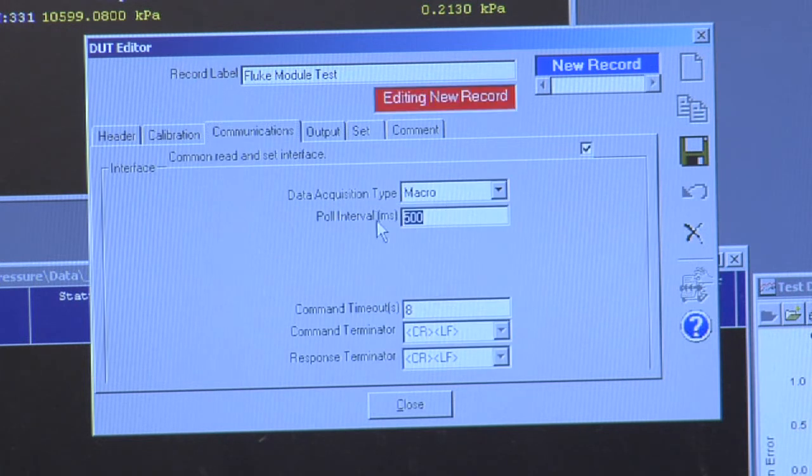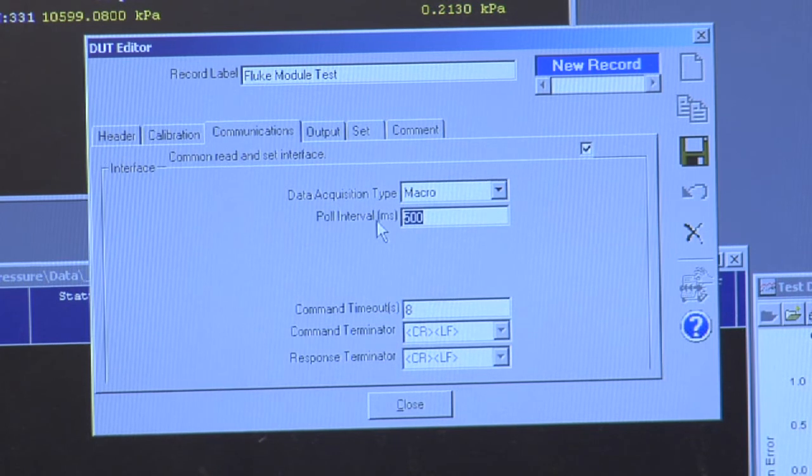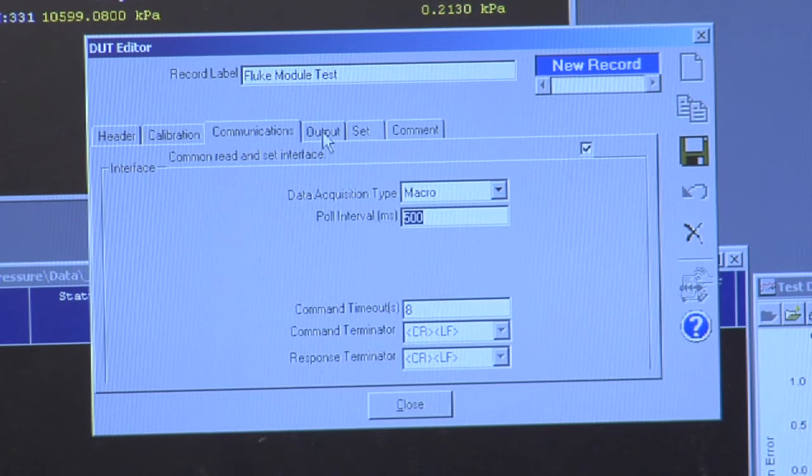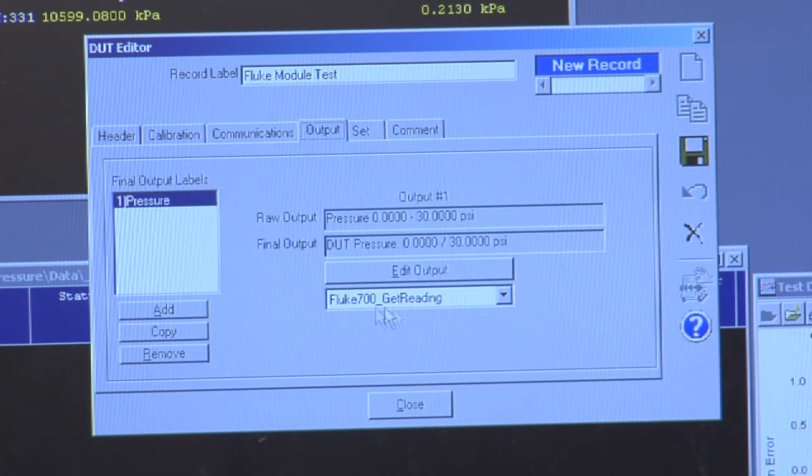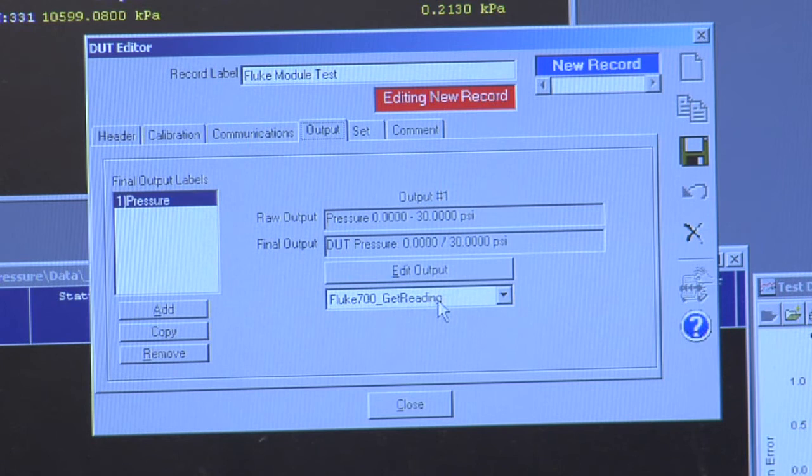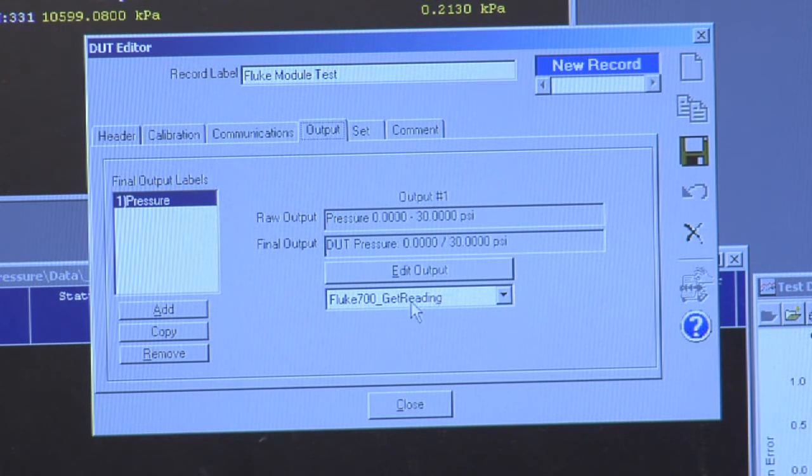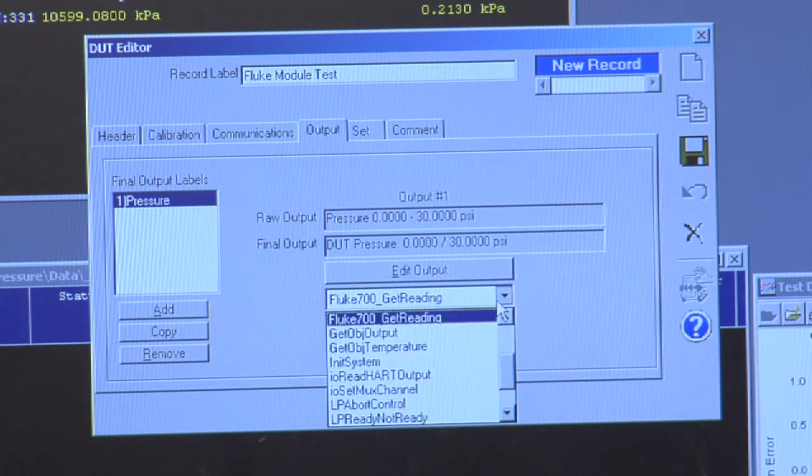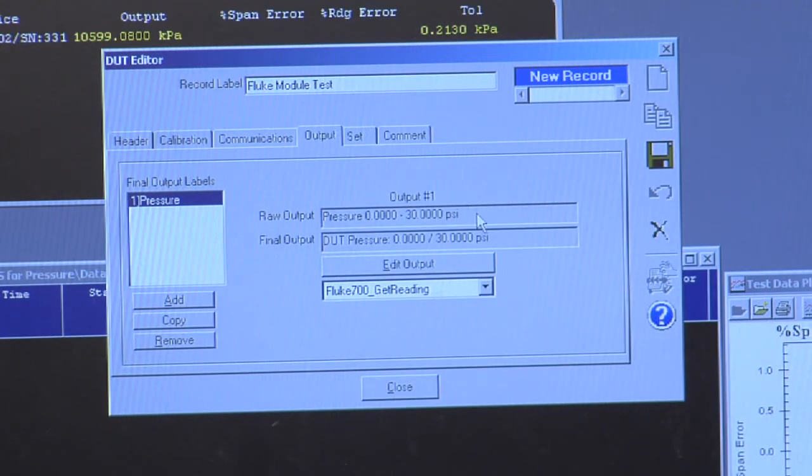This macro runs every 500 milliseconds. It calls this Fluke700_GetReading custom macro. And that concludes the specifics of the setup for this pressure module.